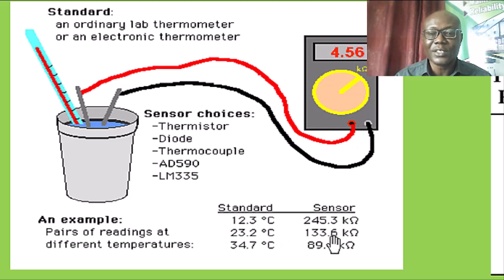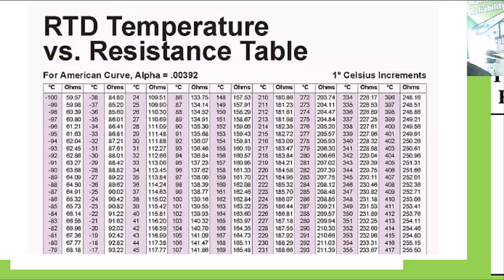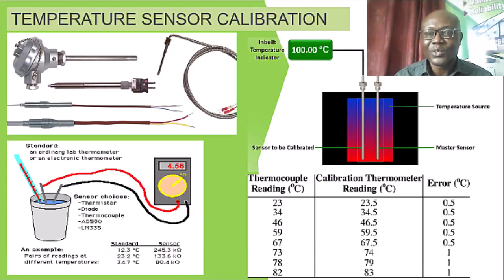Take it to this, this is the resistance. Take it to this, this is the resistance. So it has a negative coefficient. So you compare this with what we have on the data sheet, the resistance table of that particular RTD, resistance temperature detector. Okay, so if they are within range, fine. They are within limit, fine. But if not, it means that we need to replace those temperature sensors.